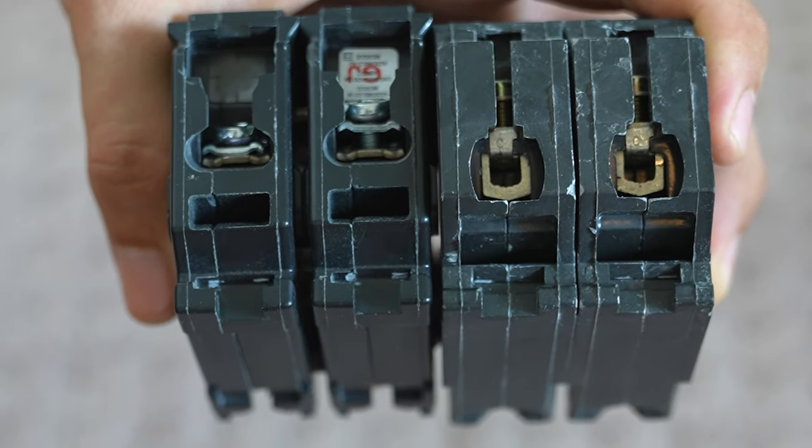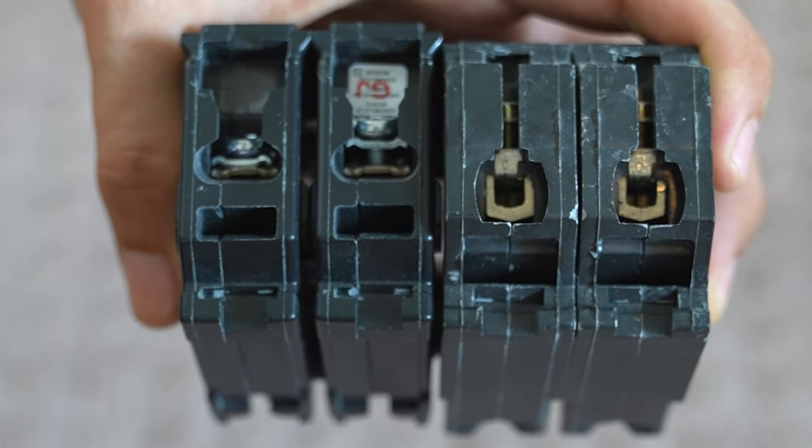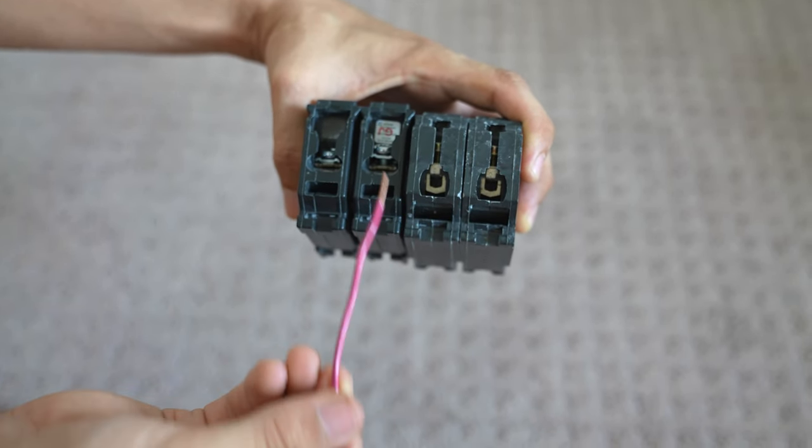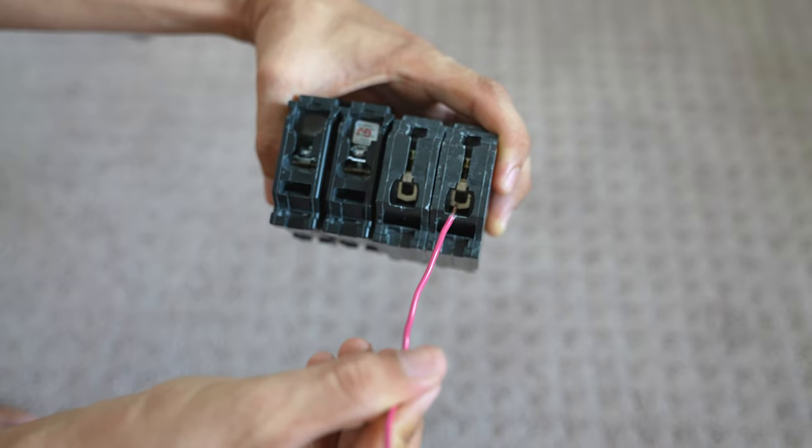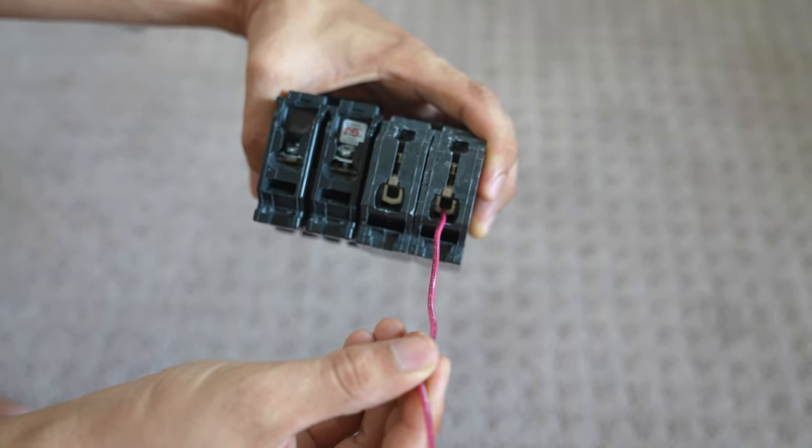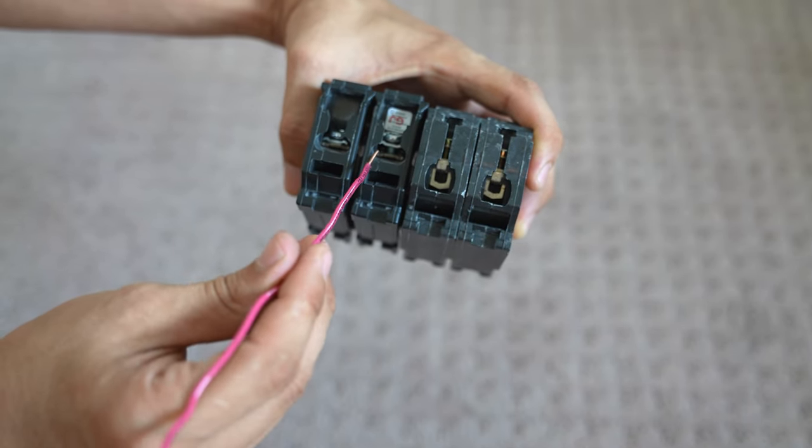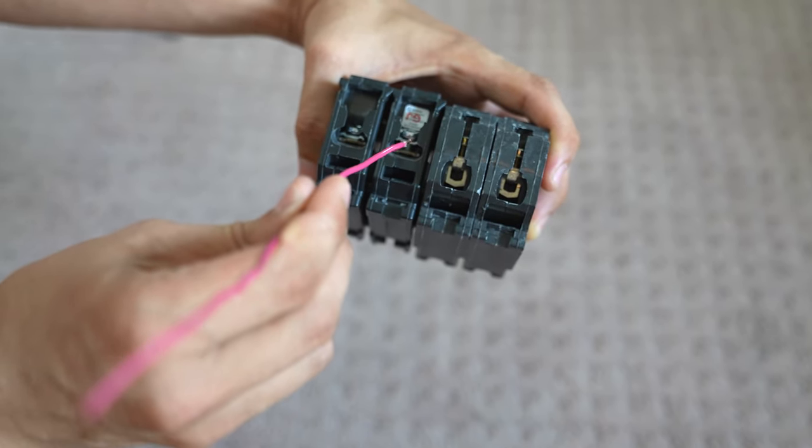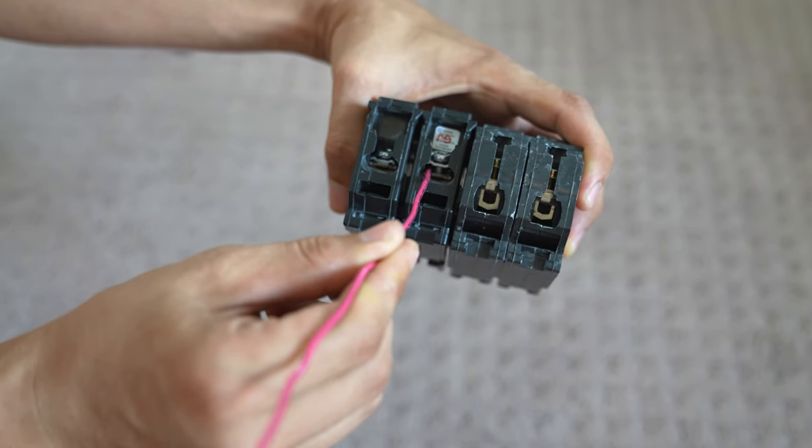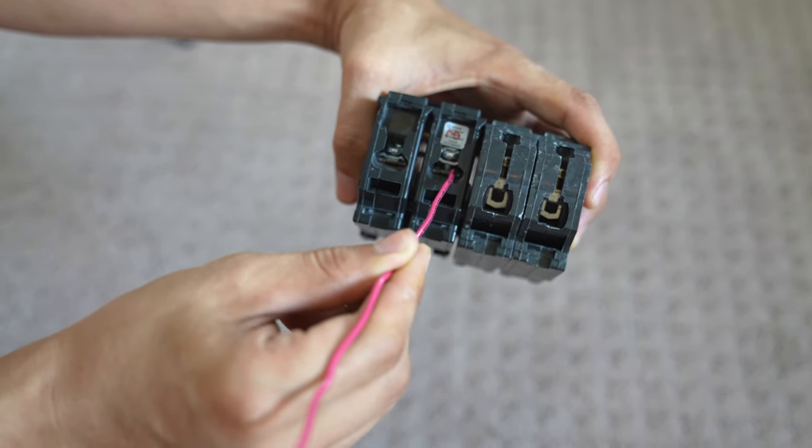There's two main kind of screw terminals on these breakers. One of them have these plates, and the other ones have this clamp-down feature. So the clamp-down ones are really easy. You just put the wire in the hole, and as you're screwing the screw in, it clamps down on the wire. Whereas these plate ones, you just have to make sure that you're not putting it under the screw, but you're actually putting it in between the plates, the wire, and then you screw it down.